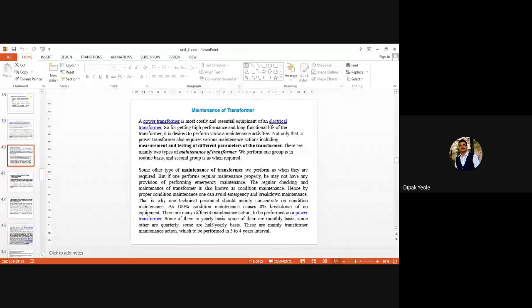Because of fault, there is overheating. Because of extra load, correct, there can be overheating. Short circuit can also lead to overheating. Again, if excess current flows, there can be chances of overheating. Or one can say insulation failure causes overheating. Due to magnetic field, it does not directly cause heat, but it causes losses such as hysteresis losses, and those losses lead to heat. Copper losses also increase, which increases the heat. So these are the number of causes of overheating, and one can make sure that whenever we limit these causes, our motor will work normally.